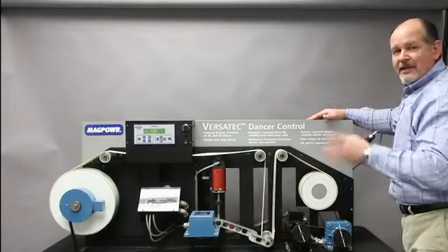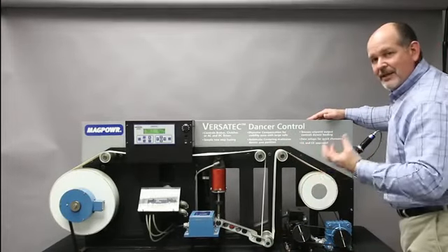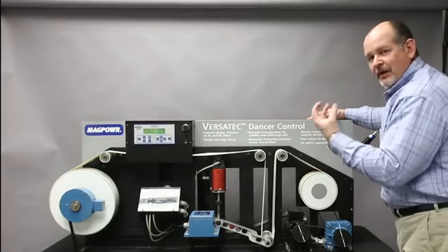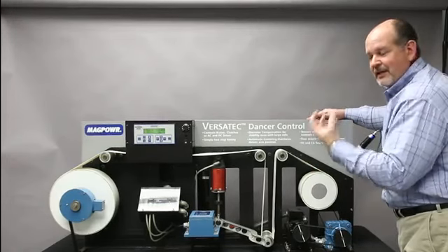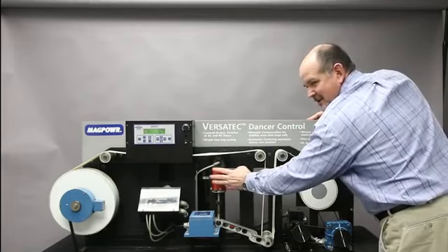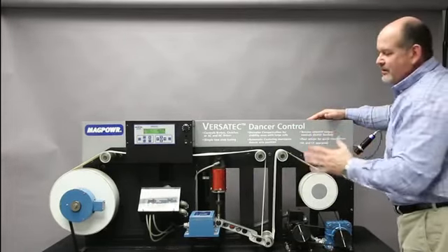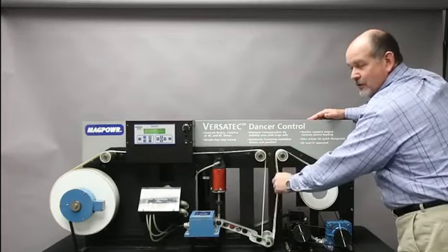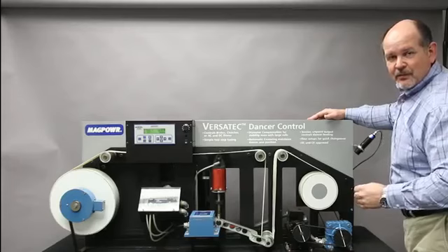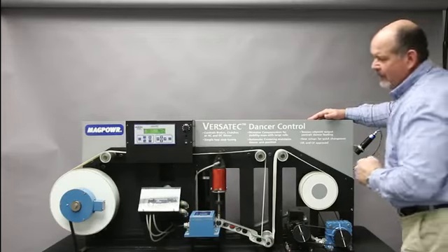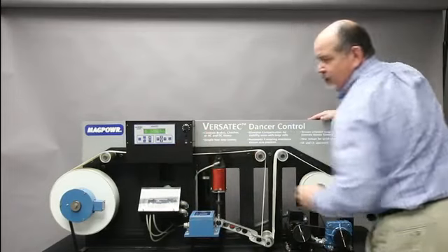Okay, so that's critical, because if you use a piston type or an O-ring type, it can actually stick, and there's a breakaway force, and all of a sudden it moves freely, sticks. Those types of things, since this is the tension, this is the load in the dancer, those transients or those sticking points will introduce tension spikes into the web. So it's very important to use a low friction type cylinder. Now let's back up and let's go to the control itself.